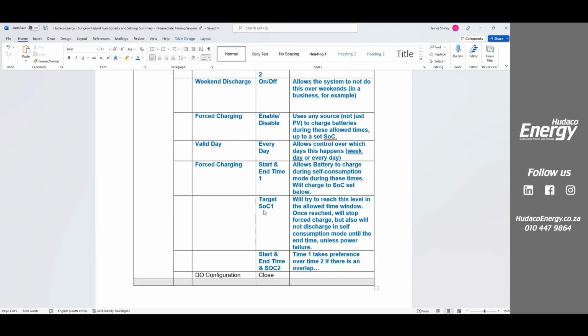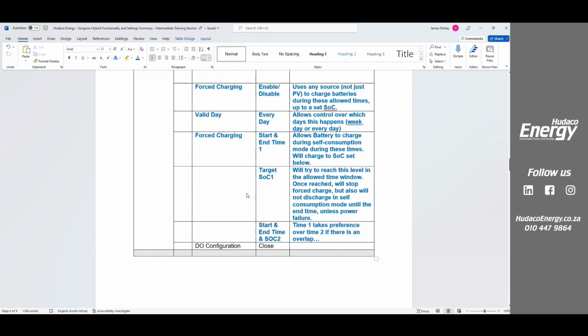So we could have a morning and an evening, or we could have an evening and a midnight, right? We've got some clients that say, well, I don't want to put in a huge battery system, and I run a lot of loads at night for security. So I want you to do one at 6 p.m. Well, let's call it from 5 to 7, something like that. And then I also want another one from 11 to 1 in the morning, just in case, so that I know if I've got load shedding at 3 in the morning, my security lights and my electric fence and everything is still going to stay up. So that would be a great example of where we would use forced charging.